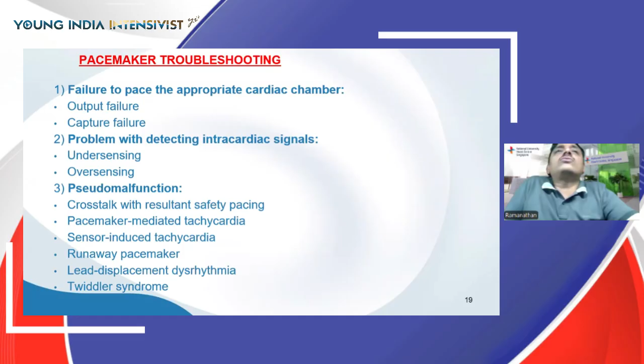So what are the general principles of troubleshooting? Of course, when you have a pacemaker malfunction, the first thing you tend to do is review it with a 12-lead ECG. You then check the integrity of the circuit. So for that, you do a proper check from the patient end to the pacing end, making sure there is no break of circuit or twisting of the circuit whereby these problems are caused. You make sure that the mode is clearly switched on, and make sure that you have pressed the right rate on the pacemaker. You check for the capture threshold, and you may have to change the capture threshold after a few days the pacemaker is being used. So again, we just spoke about how the capture threshold can be readjusted. So you essentially might have to do it as part of your troubleshooting initially.